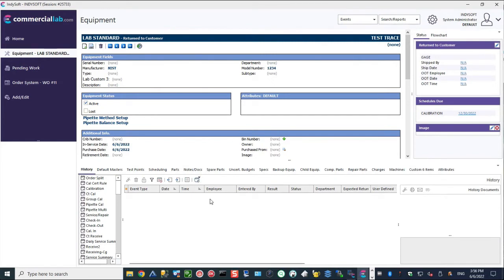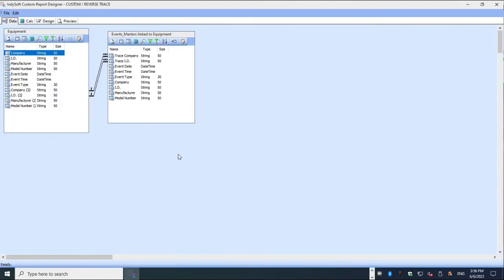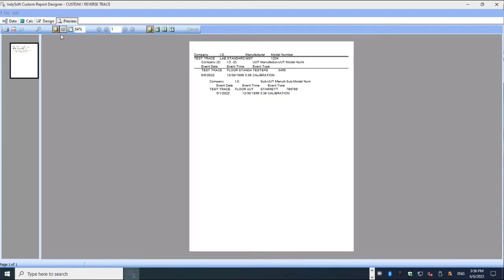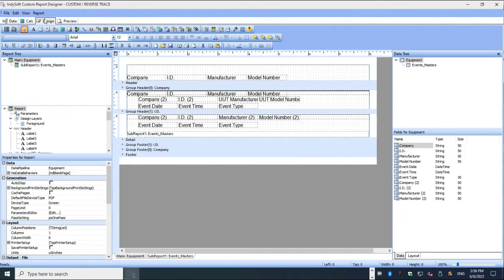The lab standard is the one that gets sent out to NIST or wherever your external cal lab is, and it comes back out of tolerance. So we would want to look at a reverse trace report to see what all it was used on. Building out the reverse trace report, you can see we have the lab standard. It calibrated the floor standard on 6.6, which calibrated the floor UUT on 5.1. And so the question becomes, how do we build that out?